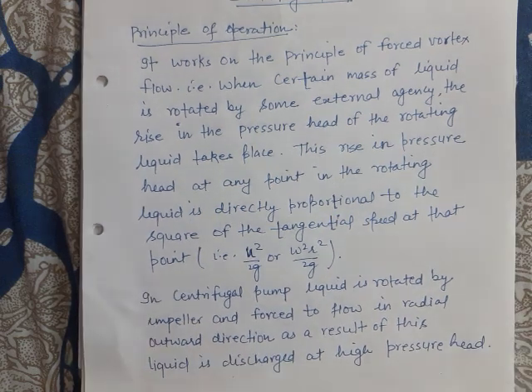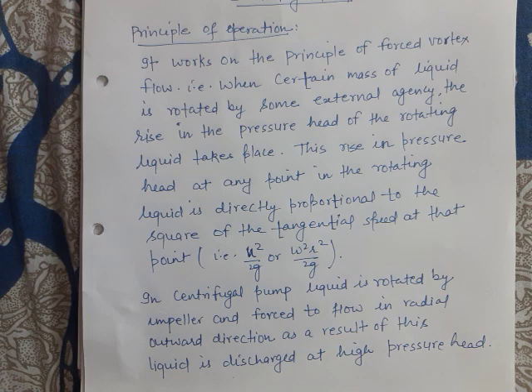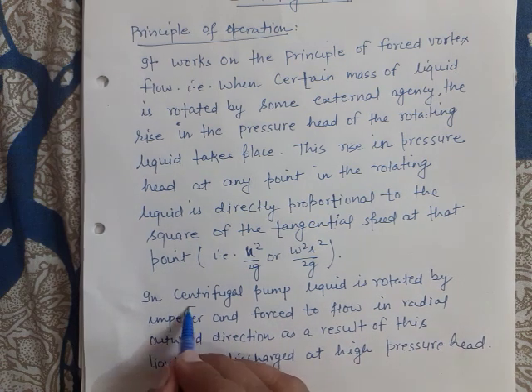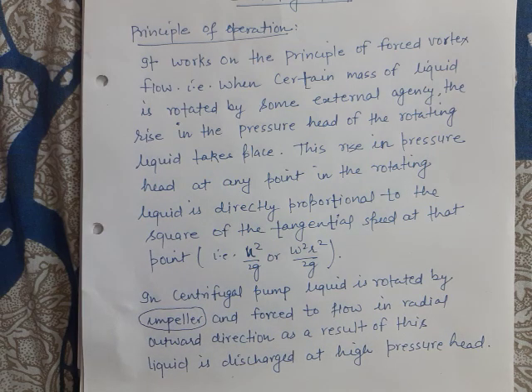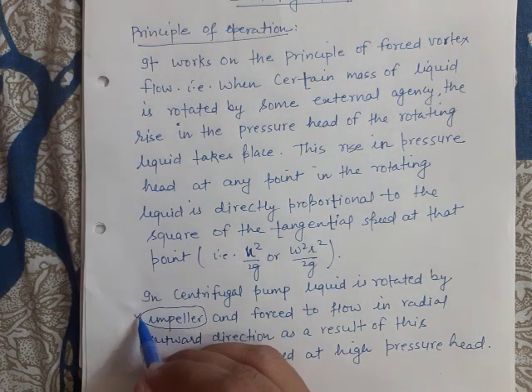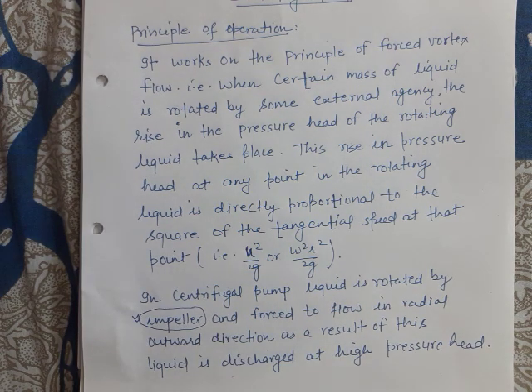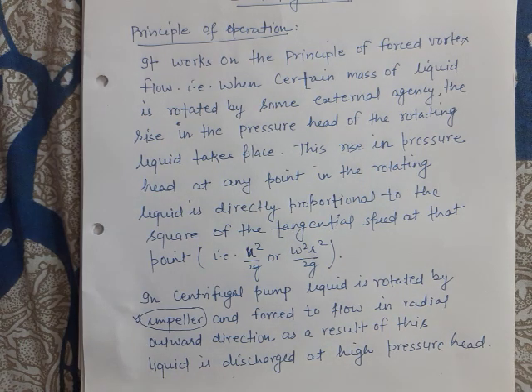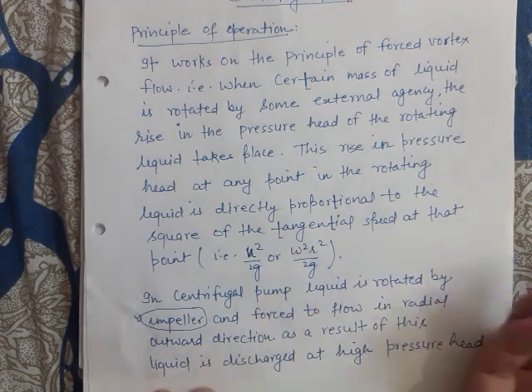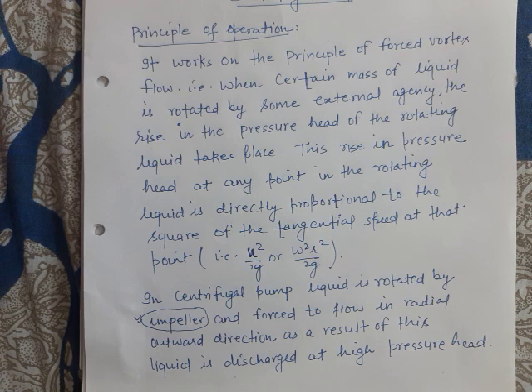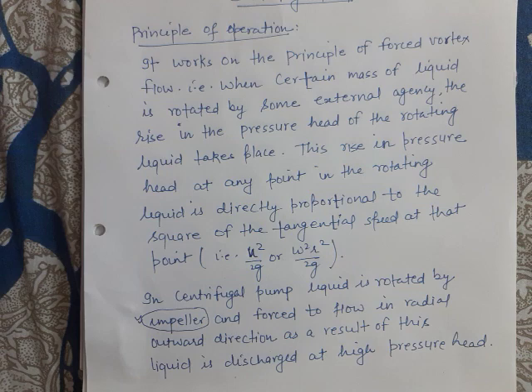In a centrifugal pump, the liquid is rotated by a rotating element known as the impeller. The liquid is forced to flow in the radial outward direction by the impeller. As a result, the liquid is discharged at a higher pressure head, because as the radius increases the pressure head also increases.